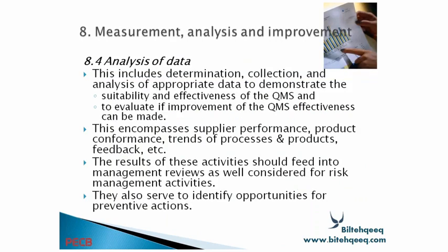The 8.4 is related to the analysis of data. This includes determination, collection, and analysis of appropriate data to demonstrate the suitability and effectiveness of the quality management system, and to evaluate if improvement of the quality management system effectiveness can be made. This encompasses supplier performance, product conformance, and trends of process and product feedback. The results of these activities should feed into management review as well as be considered for risk management activities. They also serve to identify opportunities for preventive action.